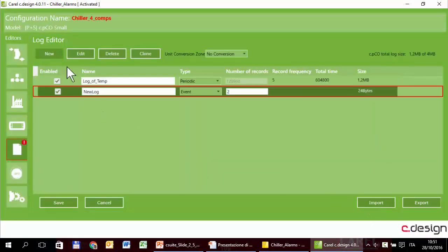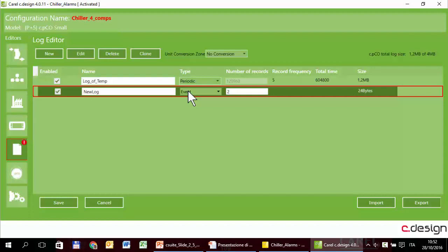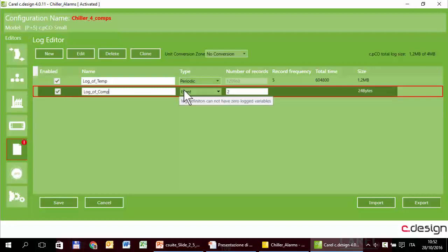Next log, that is event type. In this case probably the only log that makes sense in this application is the log of the status of the devices. So we can log the status of the compressors. Every time a compressor starts or stops we can log its status. So I will call it log of compressors, event type.